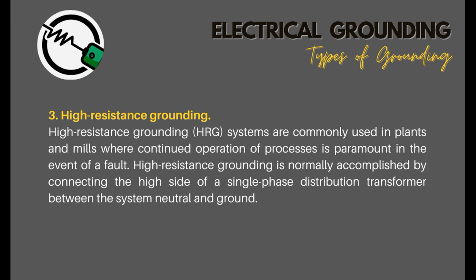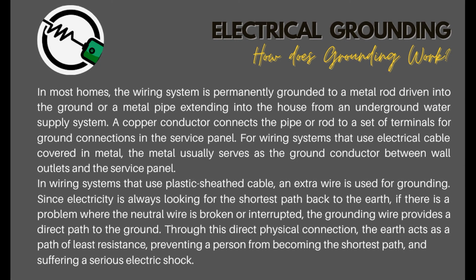High resistance grounding, HRG, systems are commonly used in plants and mills where continued operation of processes is paramount in the event of a fault. High resistance grounding is normally accomplished by connecting the high side of a single-phase distribution transformer between the system neutral and ground. How does grounding work?